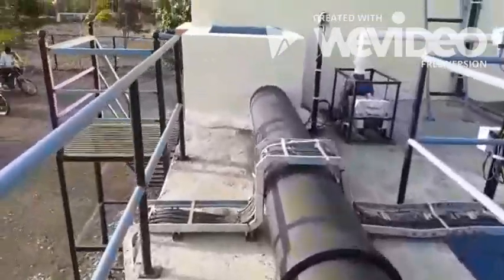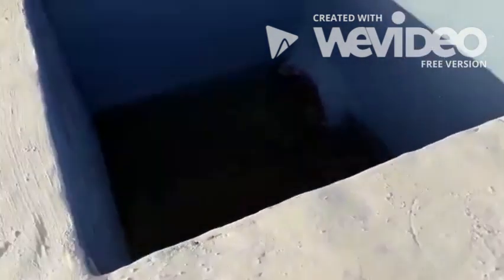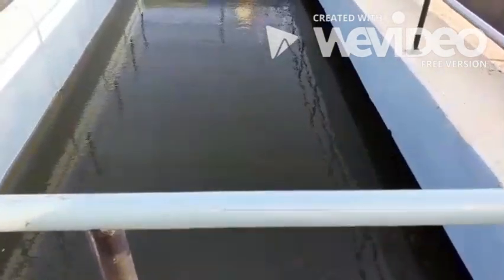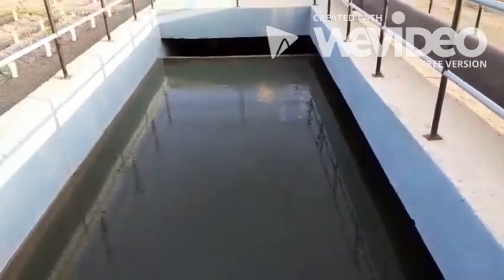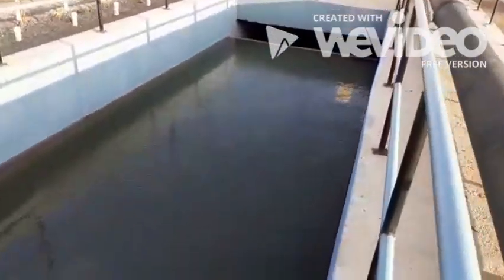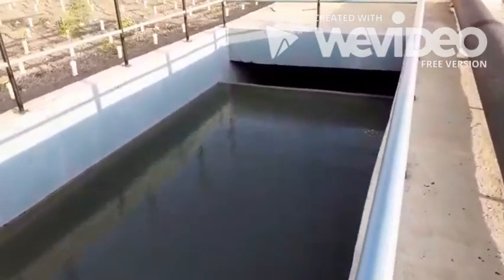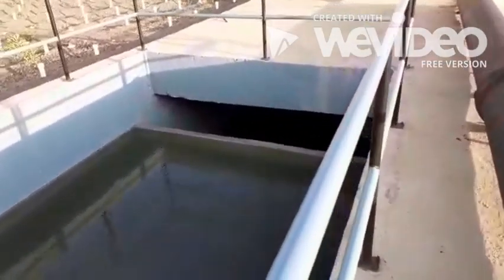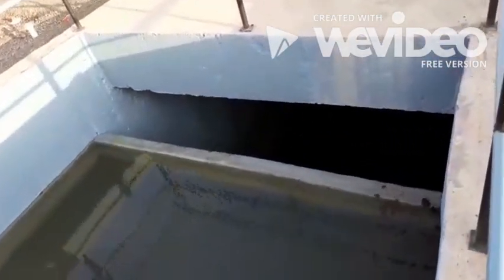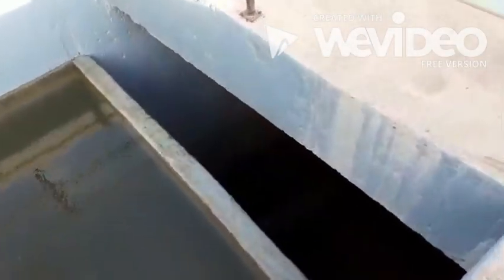Here, the water enters the inlet weir of the tube settler and goes downwards. And here it rises up through the tube settler pack, and the suspended solids in the sewage are removed at this stage. As you can see, nearly clear water is going into the next tank, which is the equalization tank.